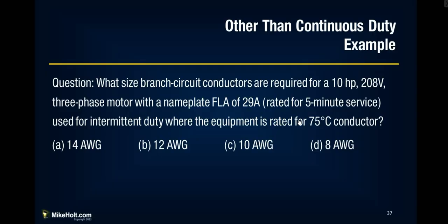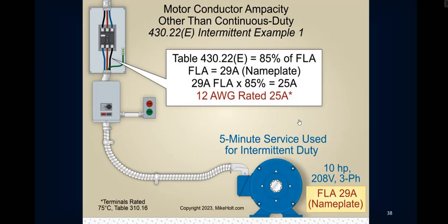We have, let's see, used for intermittent duty. Okay, well, you look at the descriptions, the classification of the service on the left-hand side, intermittent duty, 85%. Once you've done that, 29 amps times 85% gives you 25 amps. That being said, from table 310.16, that's going to give you a number 12 AWG conductor rated at 25 amps.